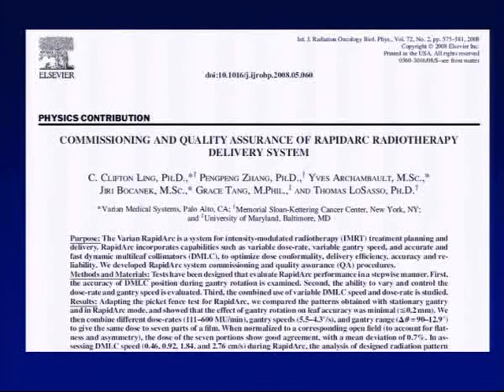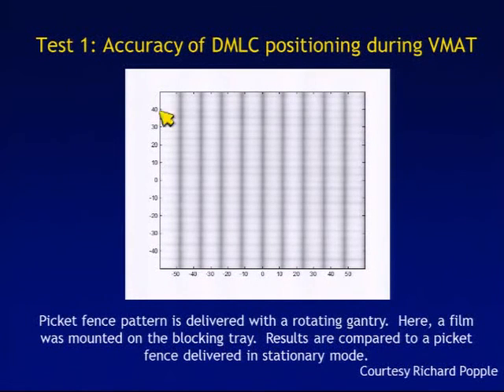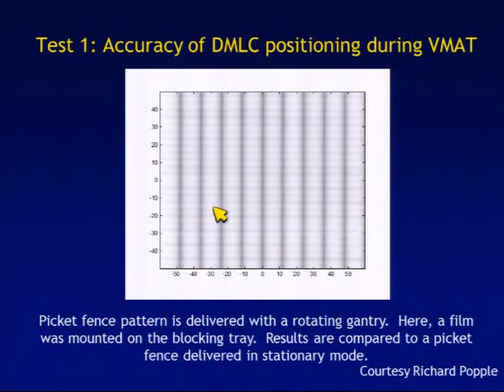The most commonly referenced document is a paper from Cliff Ling and colleagues at Memorial Sloan Kettering, entitled Commissioning and Quality Assurance of a RapidArc Radiotherapy System. The first recommended basic test is testing the accuracy of the dynamic multi-leaf collimator motion positioning during VMAT. A picket fence pattern is delivered with a rotating gantry, with film mounted in the blocking tray, and the results are compared to a picket fence delivered in stationary mode. If the system is performing well, you'll see the same picket fence pattern regardless of whether it's delivered stationary or rotationally.